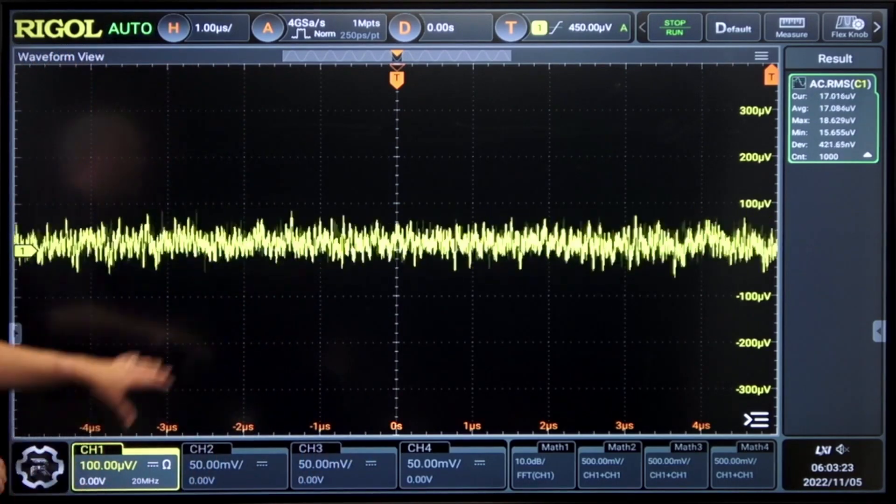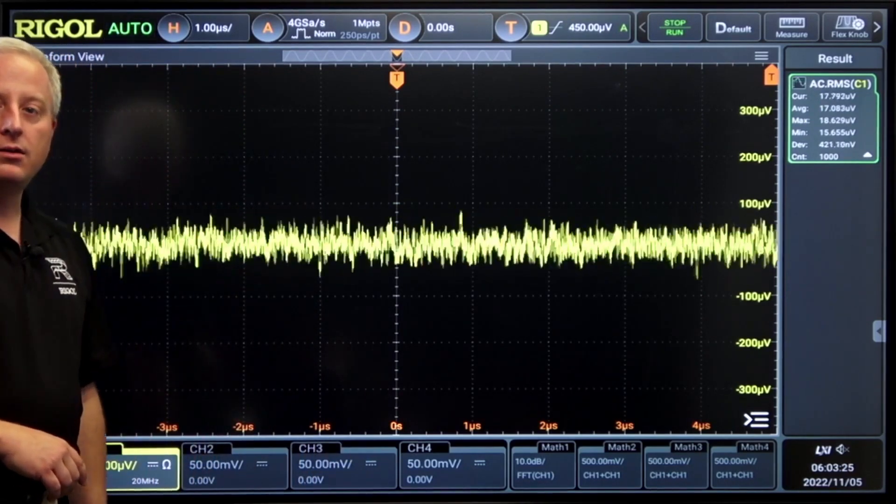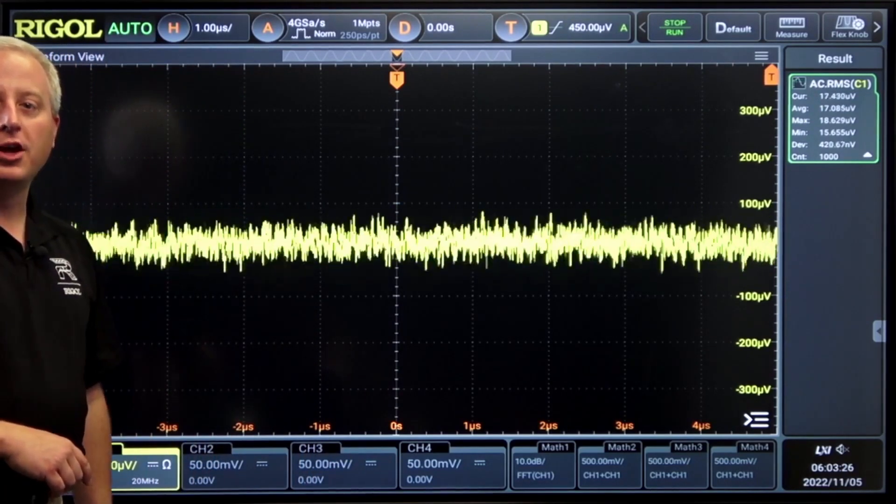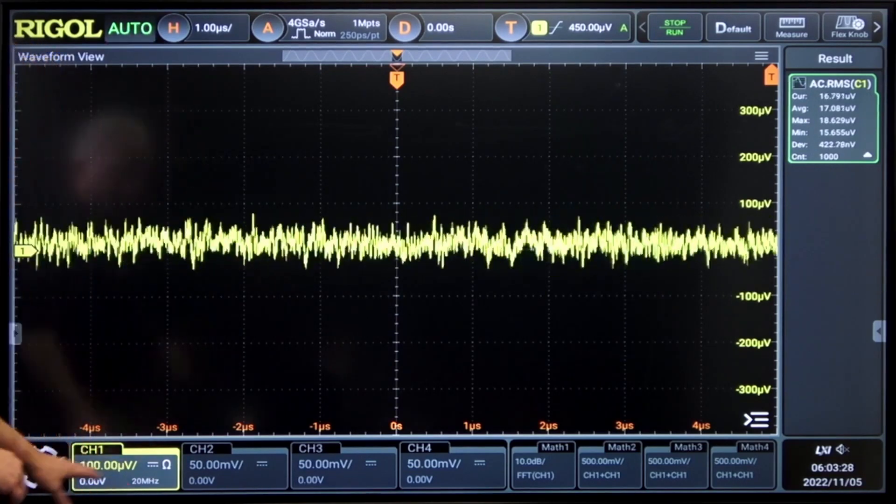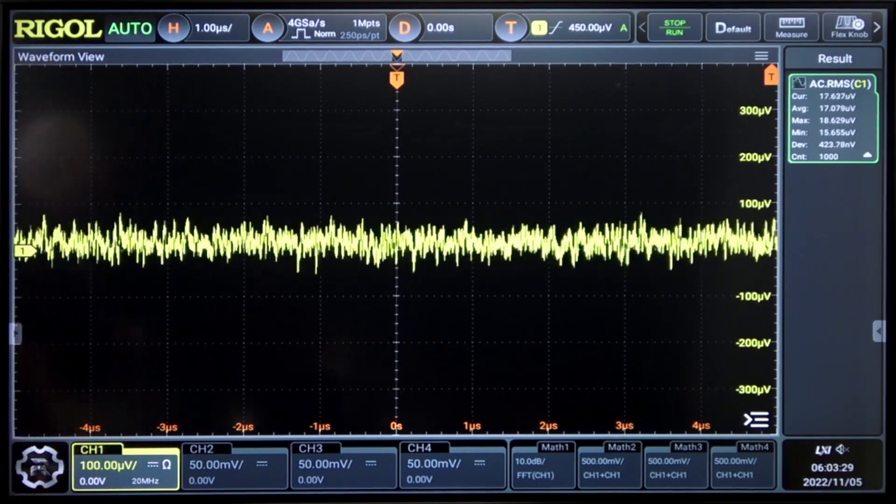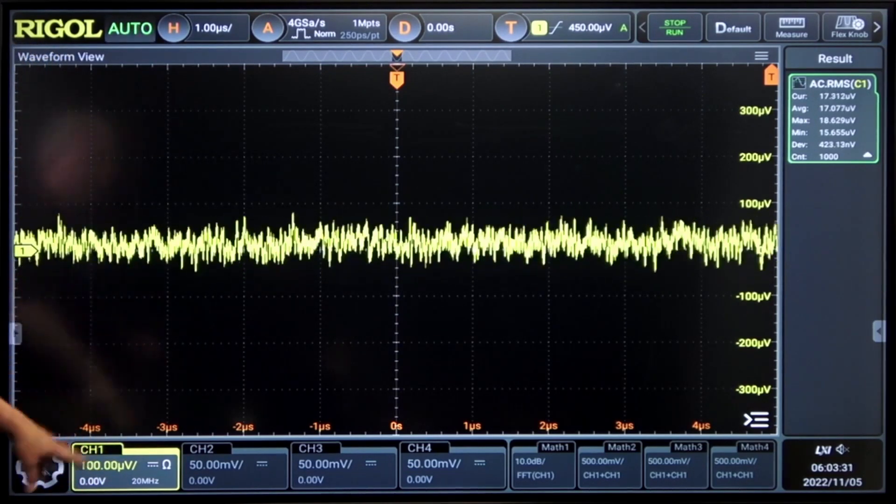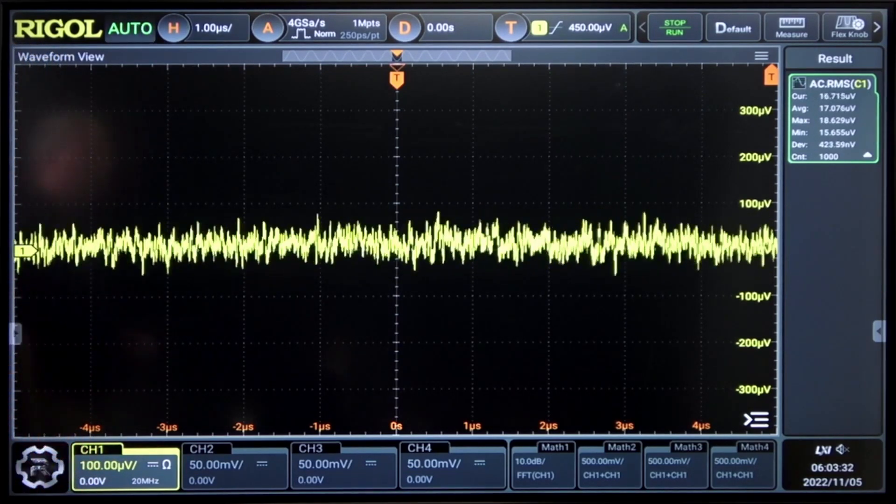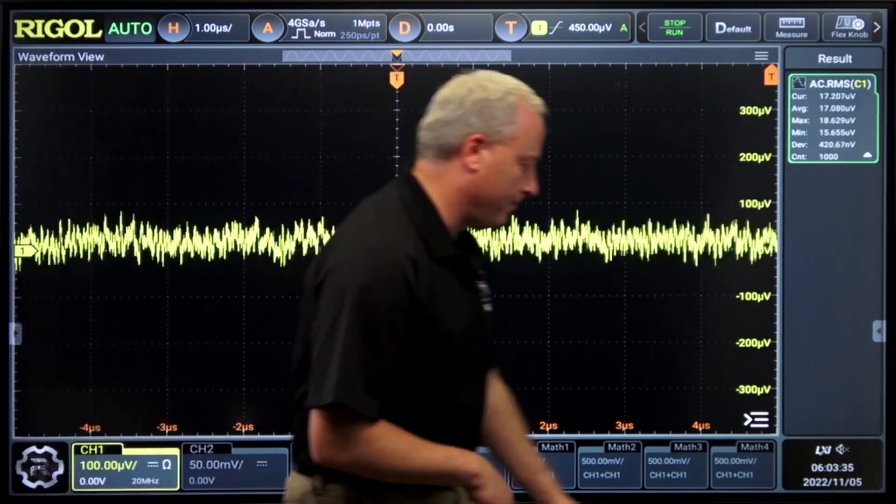First here we can see low noise down below 18 microvolts RMS on a 100 microvolt range. At this range we're limited to 20 megahertz bandwidth but we can see excellent noise performance.